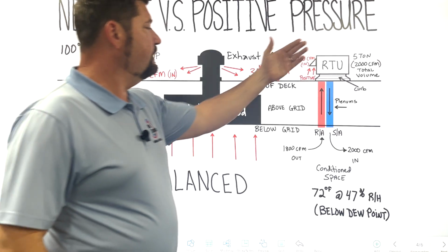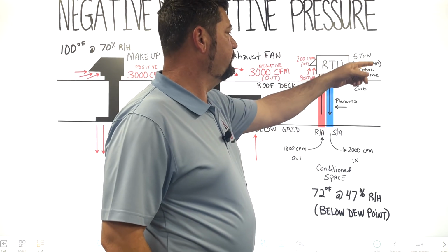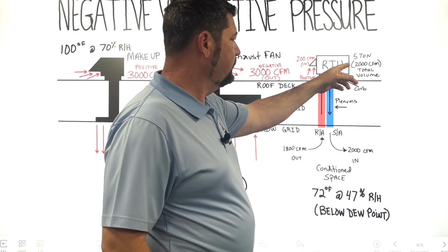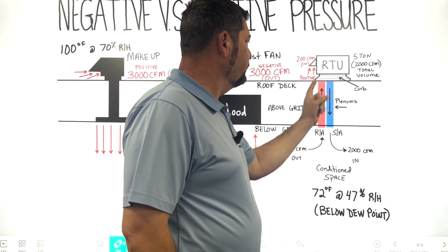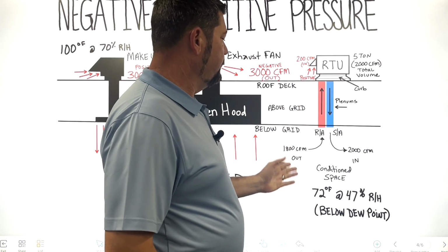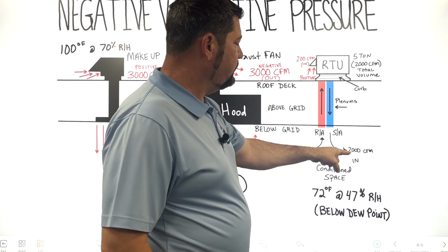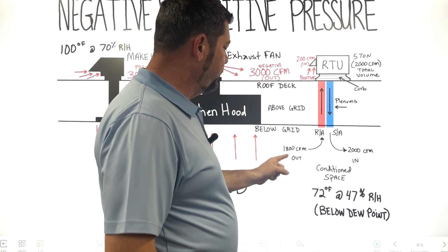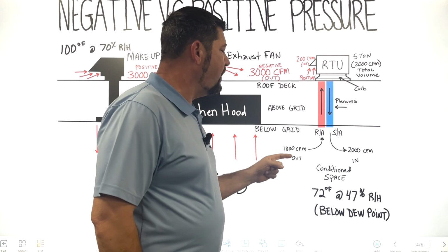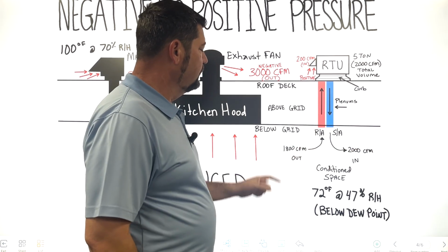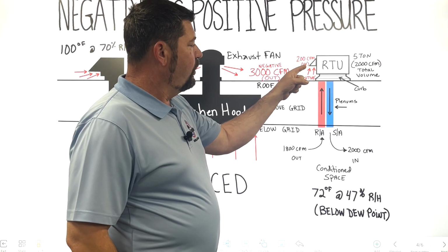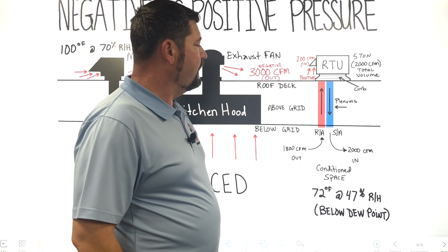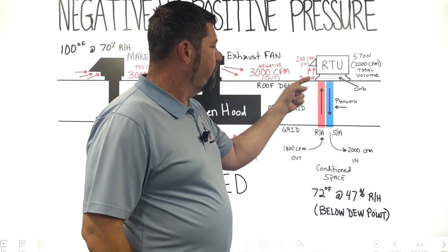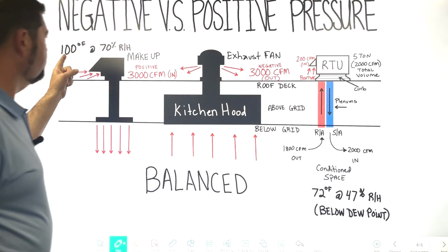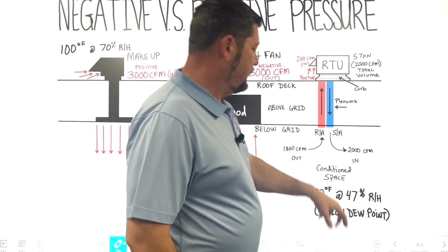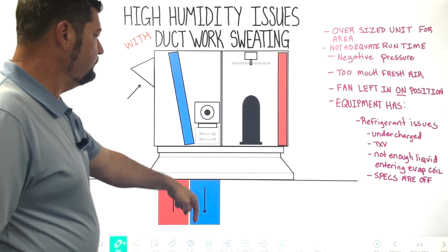And then we have the RTU. My specs here, I put a 5-ton, which at 400 CFM per ton nominal gives us 2,000 CFMs total volume that's going to move through that package unit. But if you look here, I have the supply air. There's that 2,000 CFMs going into the building. But if you look over here, I've got 1,800 CFMs coming out of the building, 2,000 CFMs coming in. And so because we have the fresh air opened up a little bit and we're adding about a half a ton of outside air in, that's 200 CFMs of positive air coming in. Yeah, it's hot, moist air coming in across that cold coil, right?